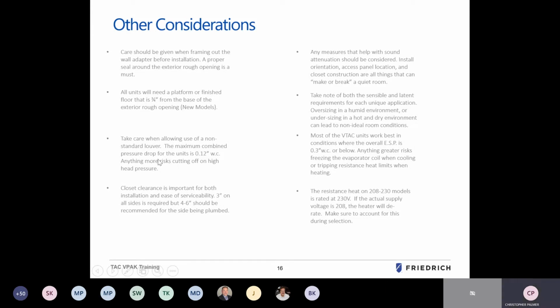Take care when allowing the use of non-standard louvers. Oftentimes it's a good idea to run it by our product management team to make sure that the opening sizes of the louvers meet the qualifications, so that there's no more than a maximum combined pressure drop of the units of 0.12 water column, or this will create a high head pressure or create restrictions, and failures of the operation of the equipment will increase. We can oftentimes look over the numbers with you to make sure that those louvers and grills, based on local code requirements or engineering specifications, meet the operational capability of the Vert-I-Pak. And we'll be happy to help you out with those along the way as those projects come across our table.